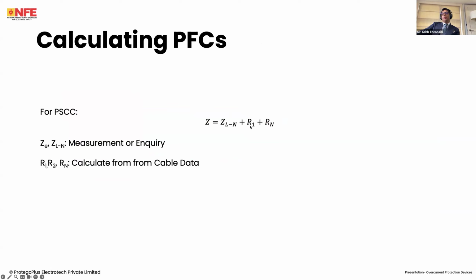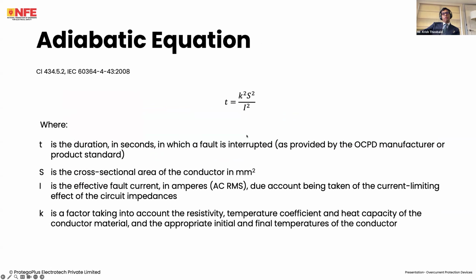I have not taken Z1 plus ZN simply because I do not want to overcomplicate things, but you get the picture. The same, you need to take into account both the resistive and the reactive part of it, so as to get an overall impedance. The adiabatic equation tells us that the time, in seconds, in which a fault is interrupted should be less than or equal to k squared s squared by I squared. What is this? K squared is a coefficient given in the standard.